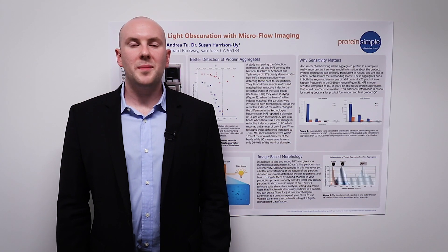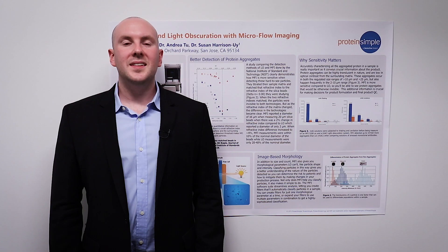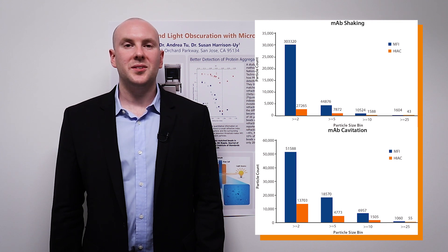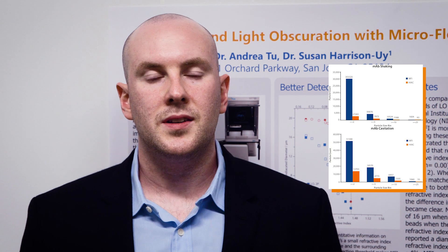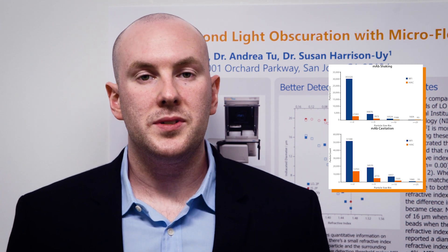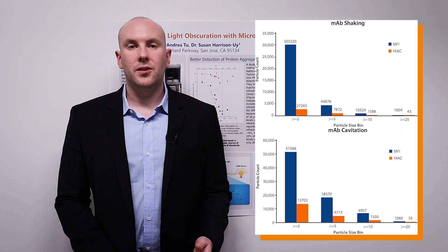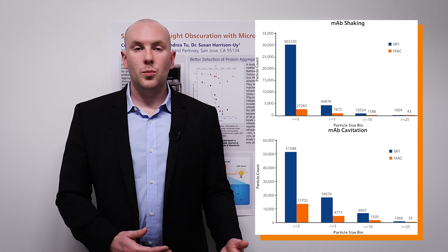This ability to measure particles with low optical contrast to their matrix is especially important for evaluating biopharmaceuticals. Protein-based products have a tendency to aggregate and form highly translucent particles, which light obscuration often misses. In this study, we compared particle levels measured by MFI (represented in blue) and the Hiac light obscuration system (represented in orange). The samples were solutions of monoclonal antibodies subjected to shaking or cavitation stress, with data represented in four size bins: greater than 2, 5, 10, and 25 microns. For both conditions and at all size bins, MFI measures far more particles than light obscuration.